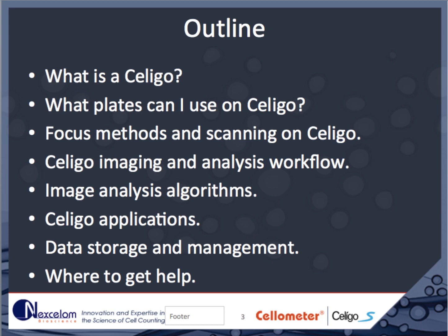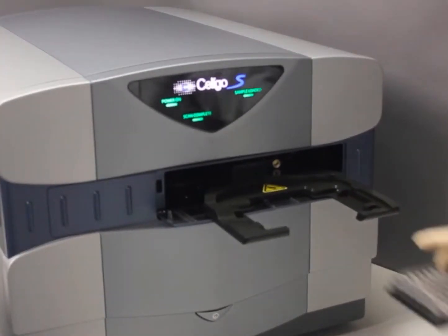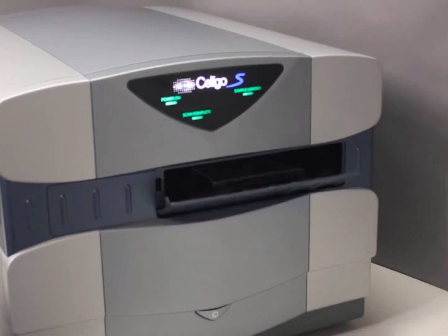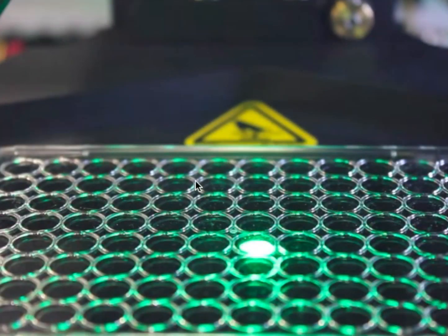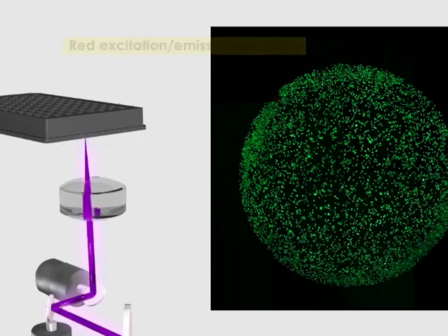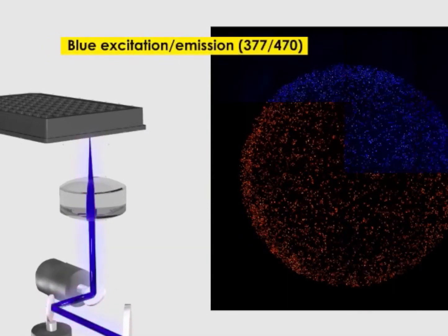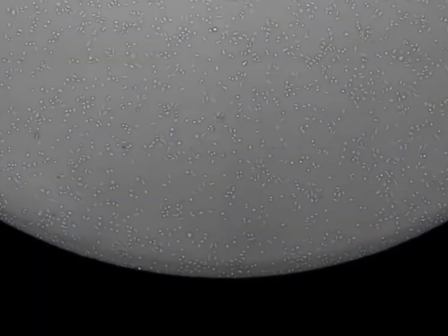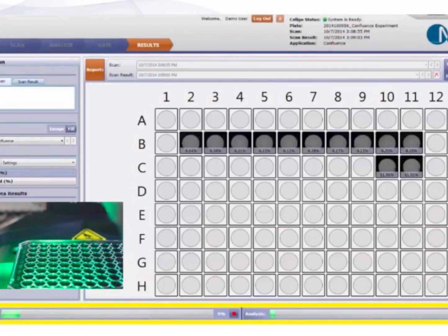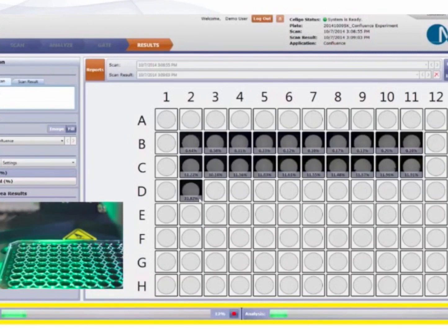The Celigo is a well-plate-based imaging cytometer. Live plates are placed one at a time in the Celigo, and the entire surface of each well is imaged in brightfield, green, red, and blue fluorescence. The high-quality stitched images are then analyzed using built-in algorithms to count every cell in every well. Analysis can be done simultaneously with imaging or, after the fact, using batch processing.